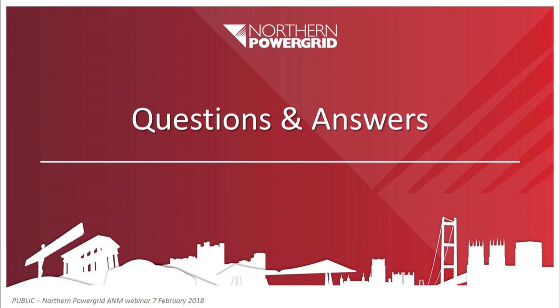With regard to the other question, are you dependent on the statement of works process? Whenever we connect generation to the network, once we've got an accumulation of generation, we are obliged to talk to National Grid to check that there's no impact on the transmission system, and Driffield is no exception in that regard. However, because we are limiting how much power leaves this network, we wouldn't expect it to lead to any thermal problems on National Grid's assets. But generation contributes to fault level, and reactive power coming out of generators has an impact on voltage levels on the transmission system. So there is an interaction there, and we always have to go through the statement of works process. We have been through that process recently for the Creyke Beck GSP that Driffield is connected to, and no issues were found at that point in time. But as more generation connects, we would have to go through that process again.